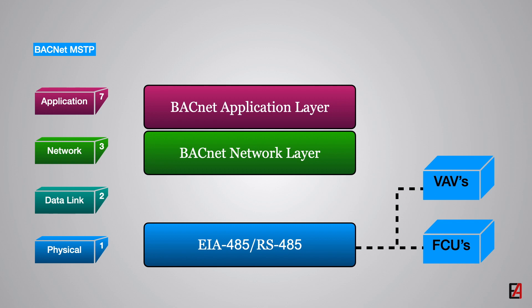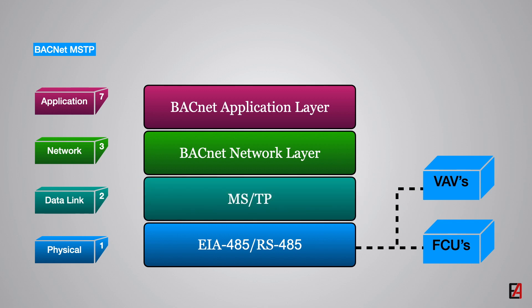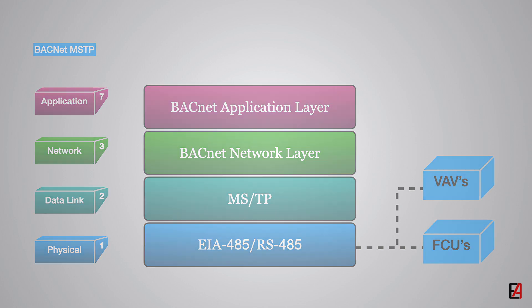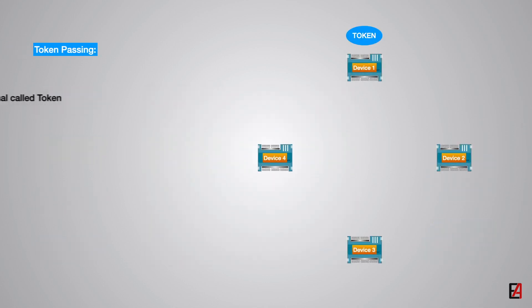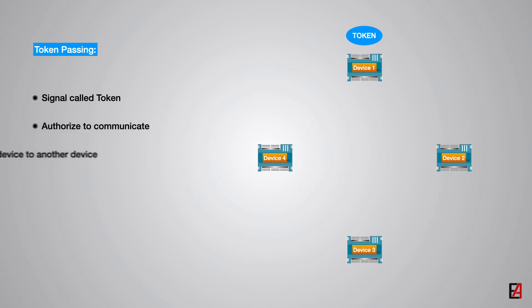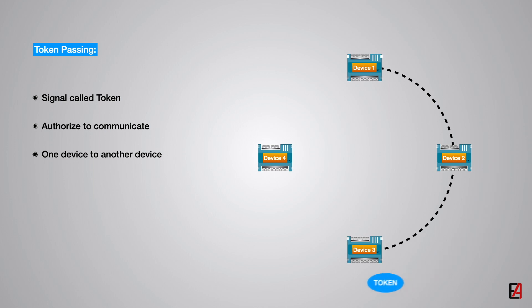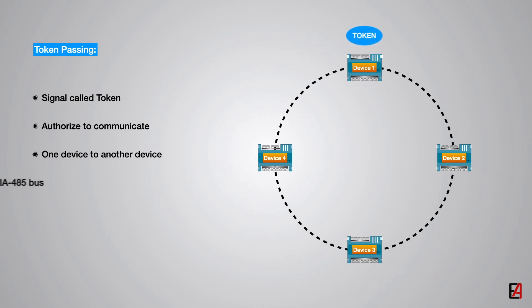Since the EIA-485 standard is a physical layer standard, BACnet defines a Master Slave Token Passing protocol to provide the data link layer function. The logical principle behind MSTP is token passing. A signal called token is transmitted to authorize the devices for communication from one device to another over the EIA-485 bus. A device can only communicate after receiving this token.